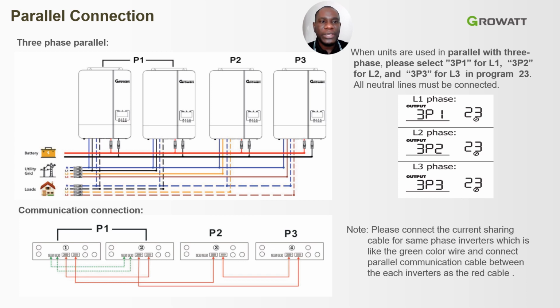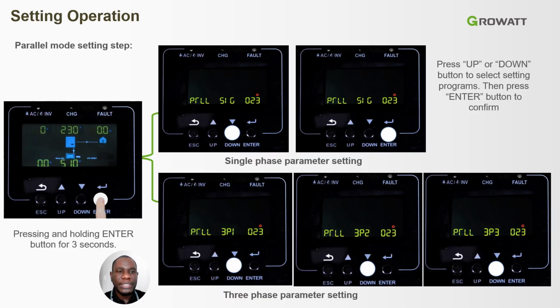Then this is a three-phase parallel system. For a three-phase parallel system, you can see from the diagram above the communication cables wiring as well. The green wire, as I said earlier, is the current carrying wire, and the red is the communication wires. You connect them accordingly as shown on the diagram. And in program 23, you select 3P1 for your phase 1, 3P2 for your phase 2, and 3P3 for your phase 3, that's your line 3. Then you need to tell the inverter that it is operating in three phase and it's a parallel connection. Then this is how you set up your inverter.